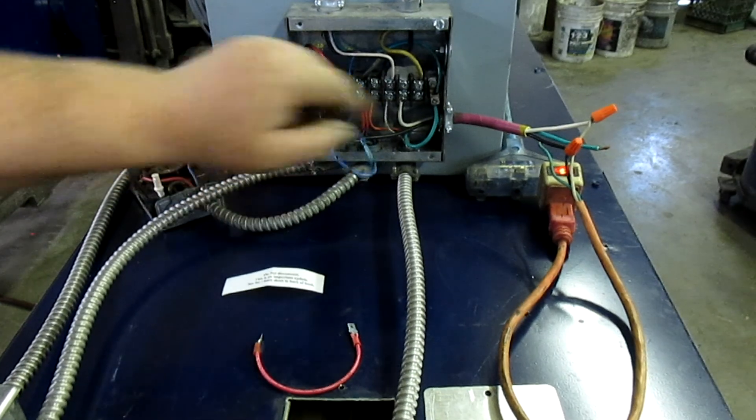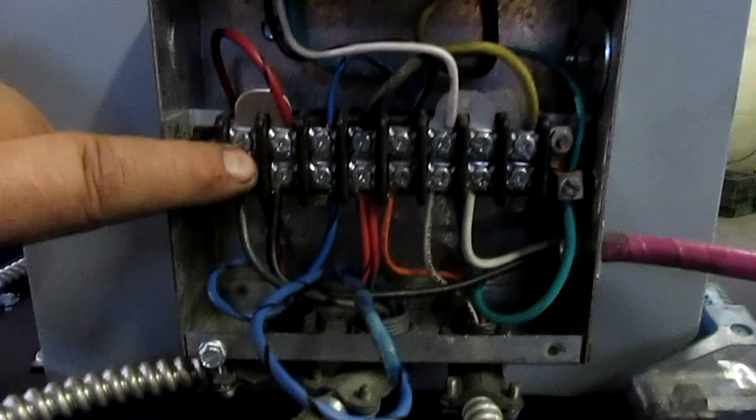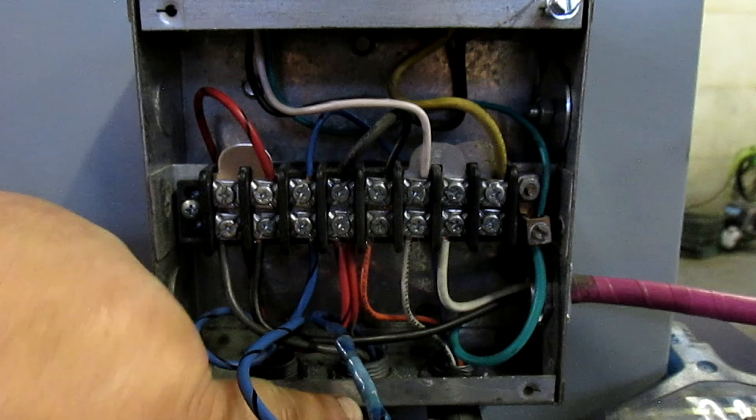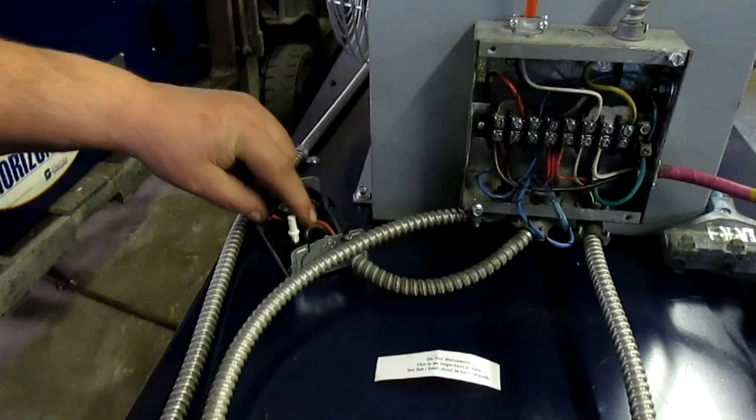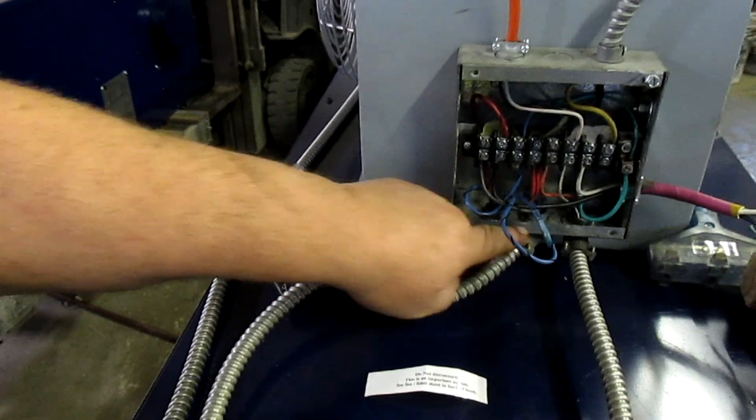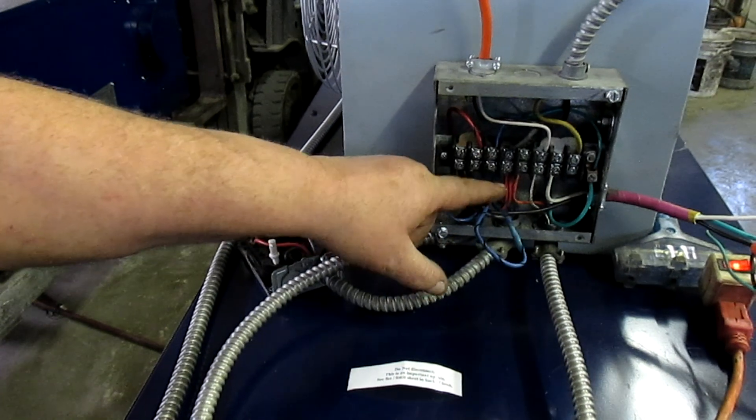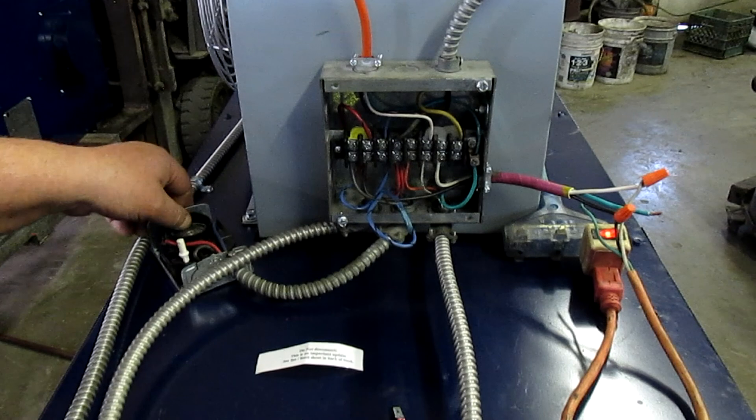Remember, we've got circuit breaker power coming in here. This one's got a jumper on, so both of these are circuit breaker power. Now when power comes in, power comes to the overheat switch first. And when this warms up, it sends power back to the red wire to run the fan motor right over here. Don't change any of that. Leave this switch just like it was.